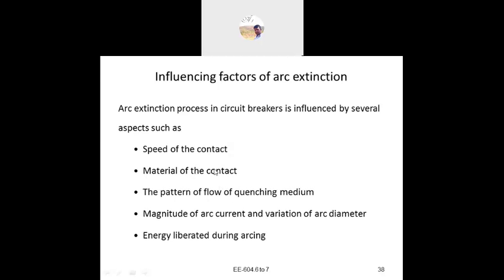If the speed of the contact is high, the arc extinction is quick. If it is slow, that is, if we are moving the contacts apart slowly, then the arc produced is also very high. Suppose there are two contacts, initially in contact. If we suddenly remove one, at that time the arc will flow. So arc extinction depends upon the speed of the contact, how fast we are moving it.